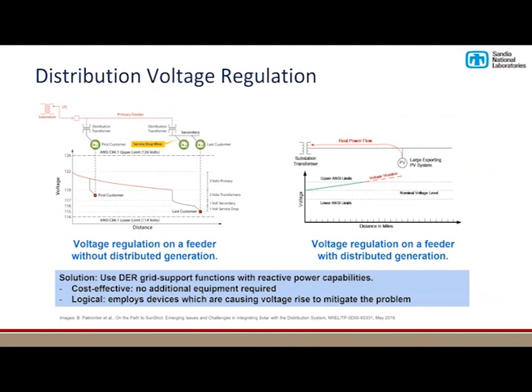So just very briefly, conceptually, distribution voltage regulation is depicted here. In traditional power systems, from a distribution substation down to the secondary, you see a voltage dropping with distance from the substation down to the end loads. I don't know if you can see my cursor, but I'll sketch it here. So if you look at your voltage, you can get lower and lower voltages. Typically, as you install PV systems, especially towards solar noon, you're injecting a lot of current, and this is increasing the voltage there.